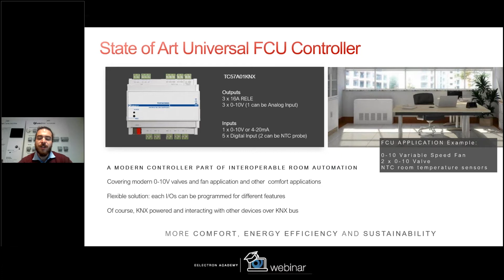So as we said at the beginning, we can wire up to 2 different probes to enable 1 or 2 different thermostats inside the device. We can use 2 digital inputs to wire and connect 2 different window contacts. In this way, we can stop the HVAC management if the window of the room is open. This can help us with the energy saving in our room.